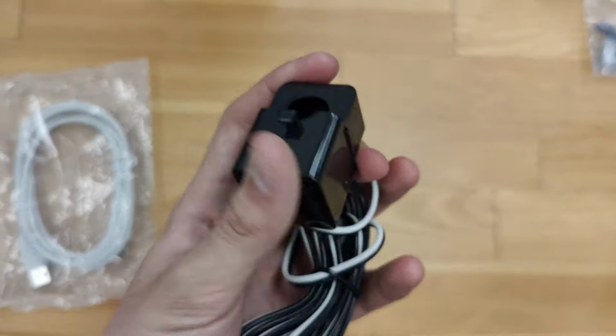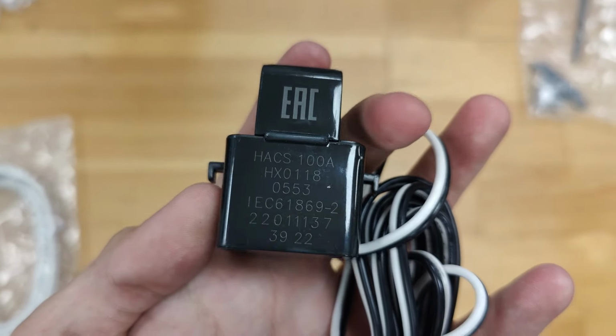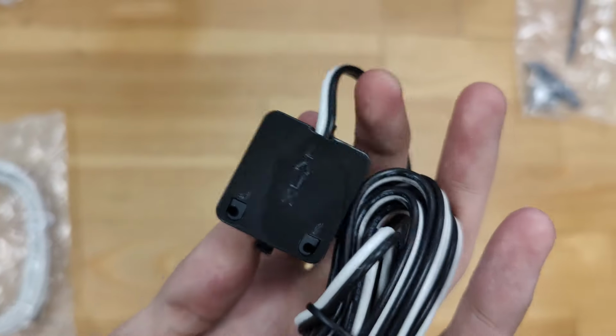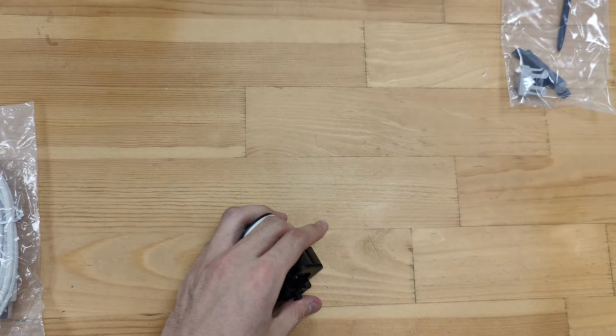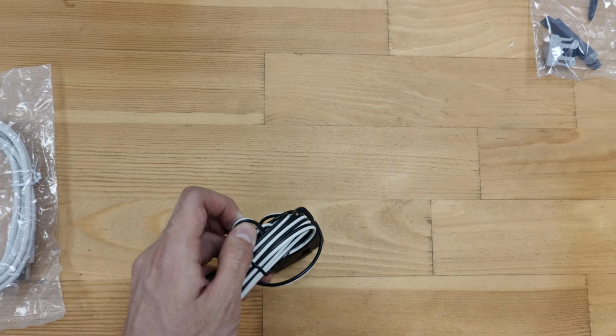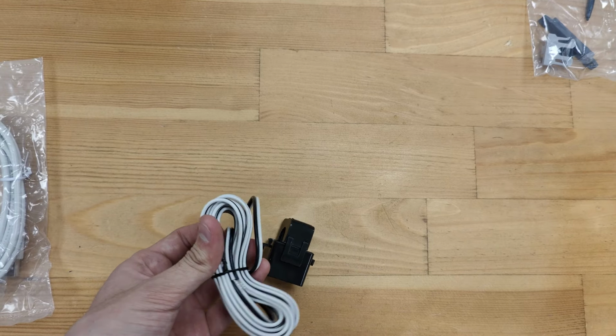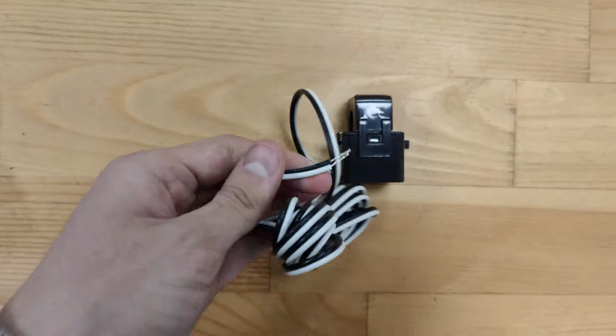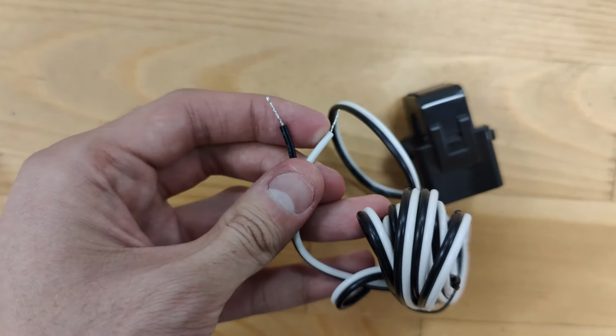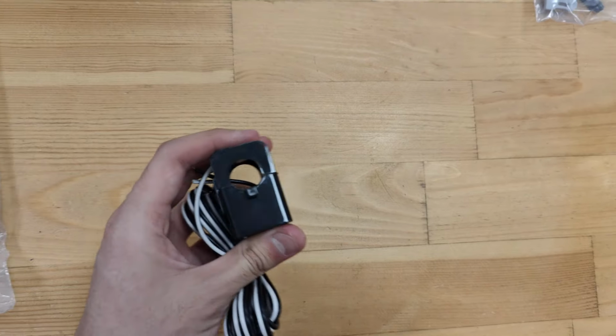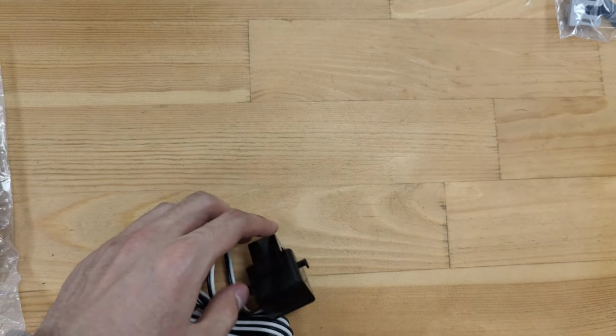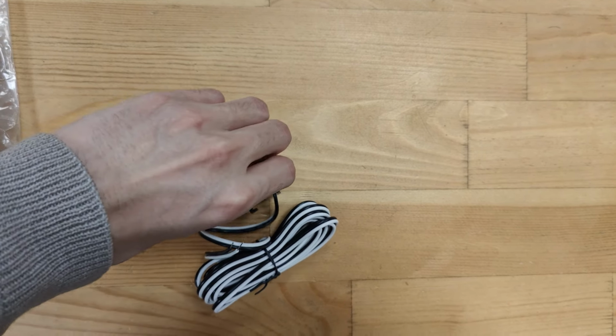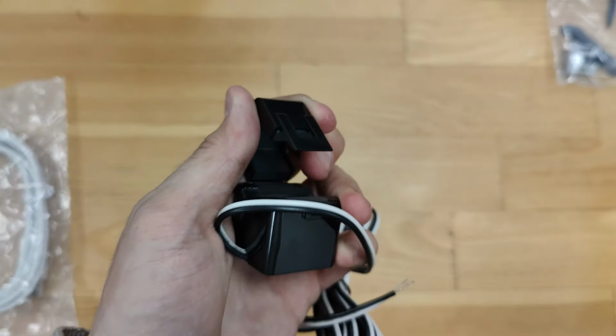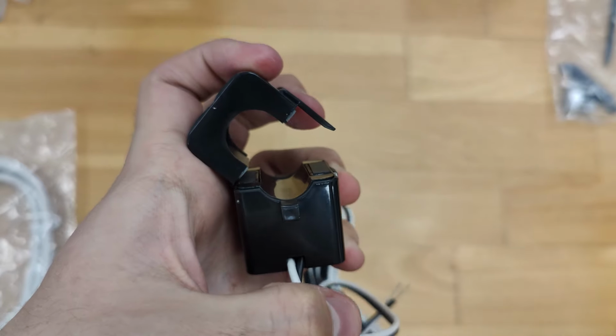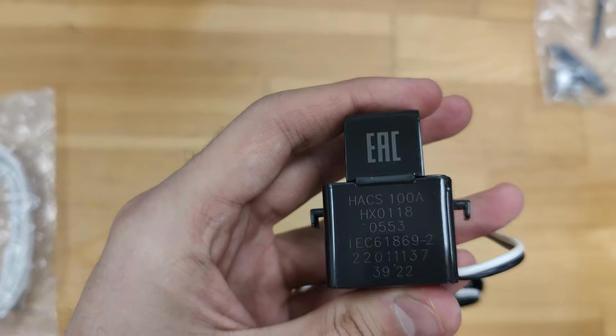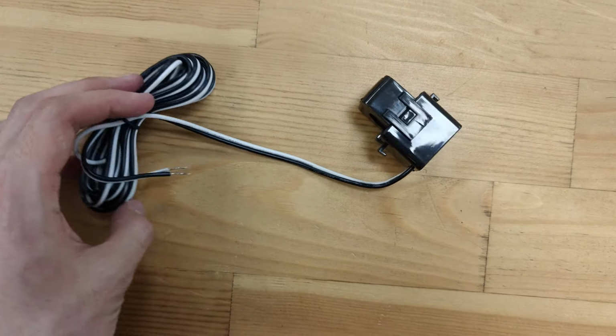Regarding the current sensor, in this case I have a 100 ampere sensor. On the body of the sensor itself it's indicated the direction of current in which it should be installed. The maximum distance to which this sensor can be connected from the BFM II is up to 300 meters. It also has two outputs. White is plus and black is minus. In the following I will show you which terminals of the BFM II are connected to which sensor. As you can see, this sensor itself is pluggable. It can be installed without disconnecting the mains load. This sensor is directly connected to a measuring circuit with a load not exceeding 100 ampere.